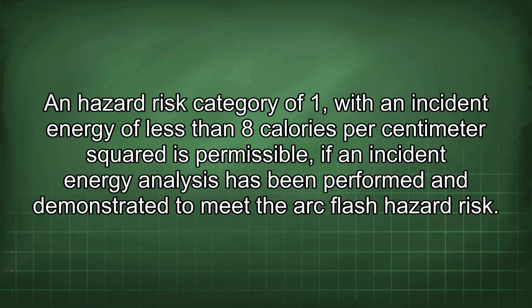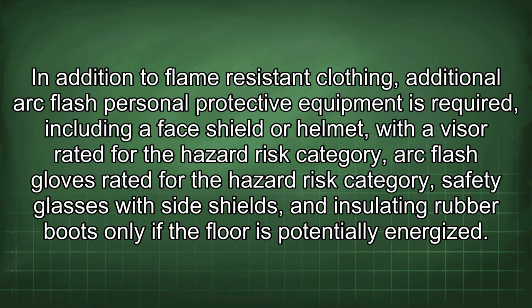A hazard risk category of 1, with an incident energy of less than 8 calories per centimeter squared, is permissible if an incident energy analysis has been performed and demonstrated to meet the arc flash hazard risk. In addition to flame-resistant clothing, additional arc flash personal protective equipment is required, including a face shield or helmet with a visor rated for the hazard risk category, arc flash gloves rated for the hazard risk category, safety glasses with side shields, and insulating rubber boots only if the floor is potentially energized.